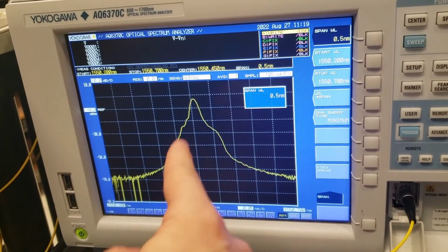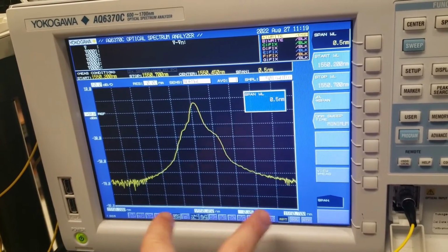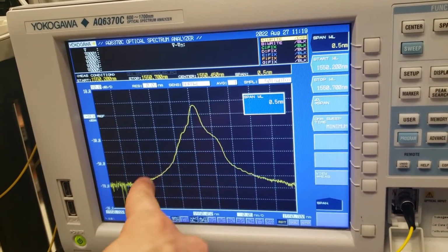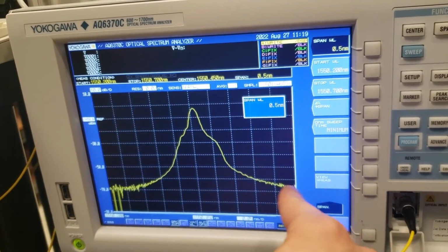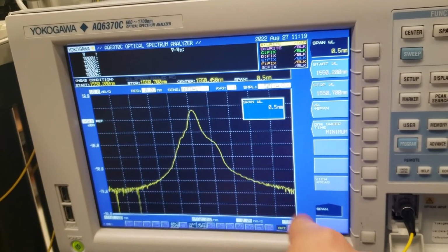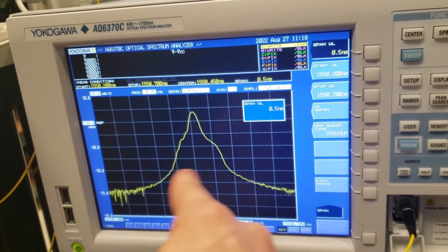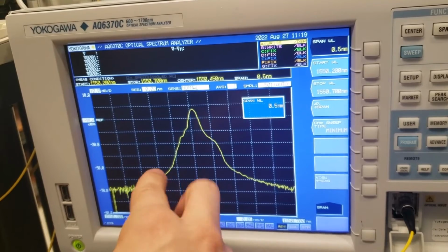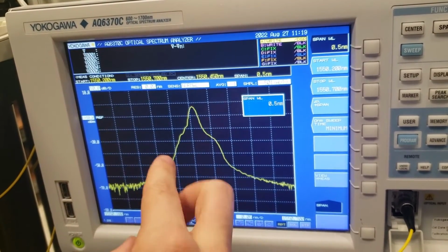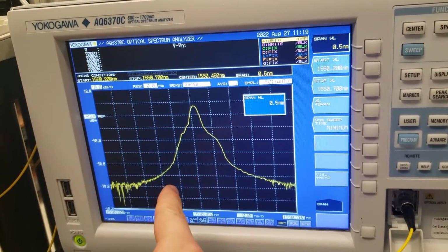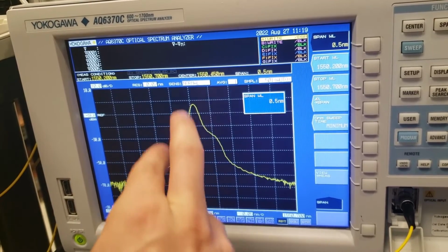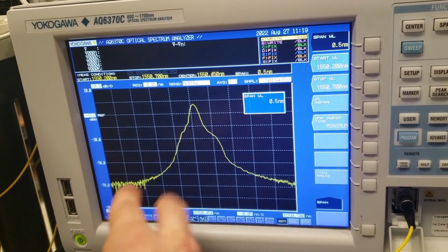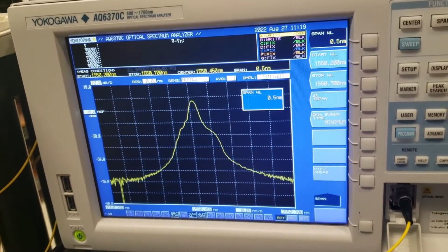We have the same measuring range here, but you can see that this peak is much more rounded. That's simply because the grating used to split up these wavelength components spatially will cause, even if you had a perfect laser sent in, a smeared out spot. That smearing out makes the line width look much larger than it actually is.